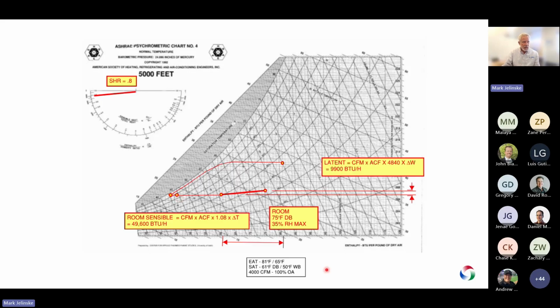But if we put 4,000 CFM of that air into the space, we would be overcooling the air. So I can reverse engineer, and assuming we needed about a 75 degree room temperature, I can see what the cooling load here is - room sensible. And then, why did they make it so cold here?